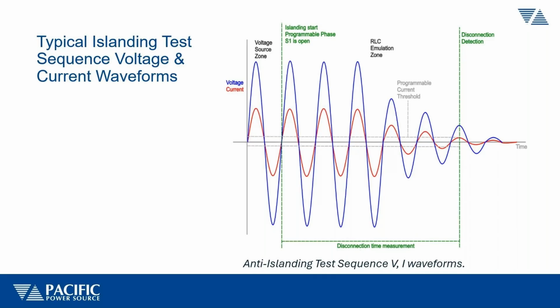So at that point, they will disconnect, and the voltage should collapse completely as the test setup is now de-energized on both sides. And at that point, the test setup will detect at what time that happened from disconnection to the grid. So that time window is critical and has to meet the test requirements of the standard.